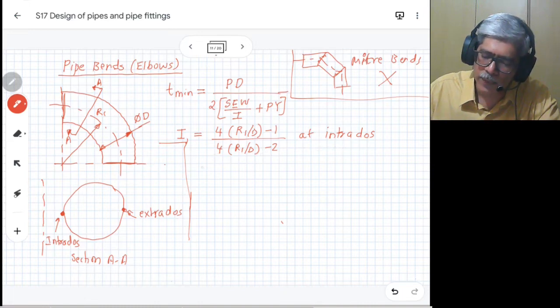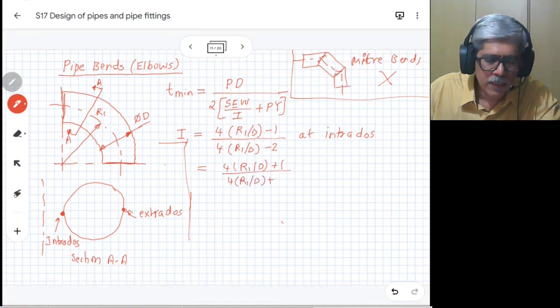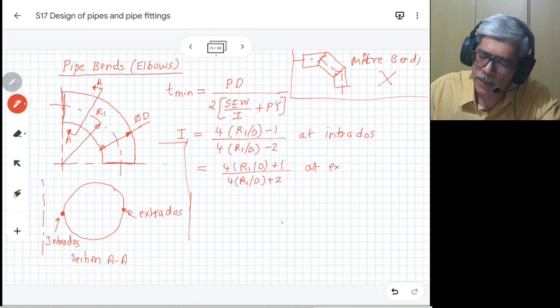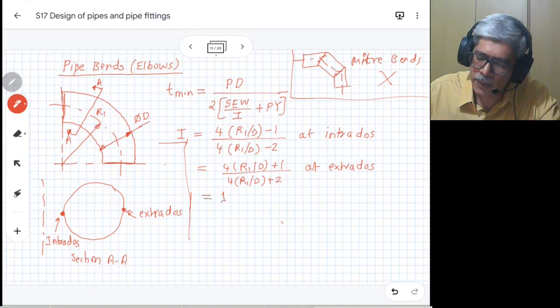As a result, both thicknesses need to be calculated and mentioned for the inspector to check. This I is given at intrados by this particular factor. It is also given at the extrados by the factor: 4(R1/D)+1 divided by 4(R1/D)+2. This is at extrados.